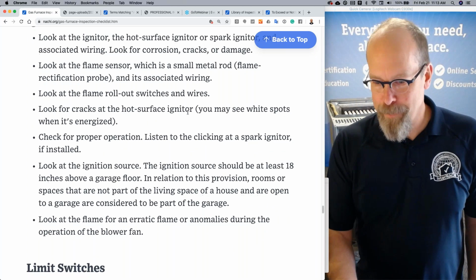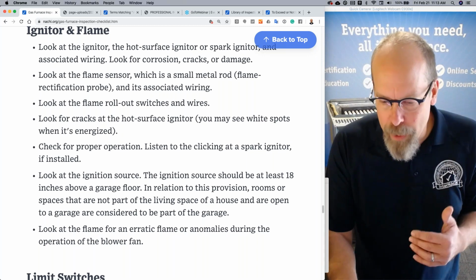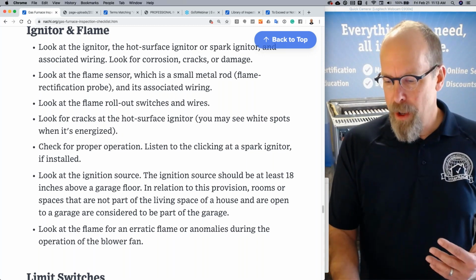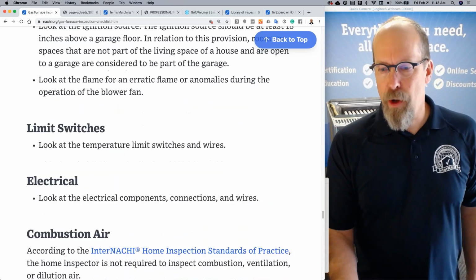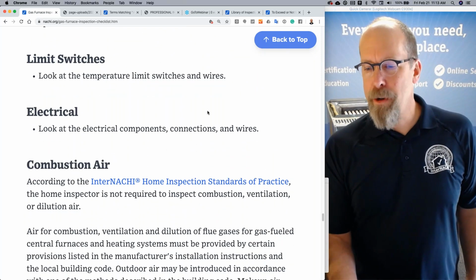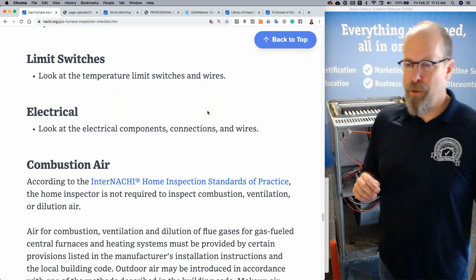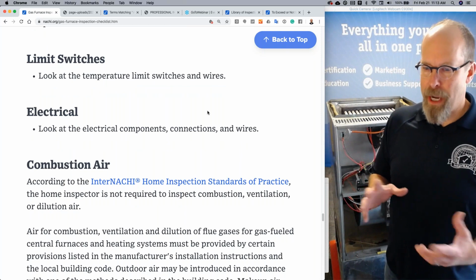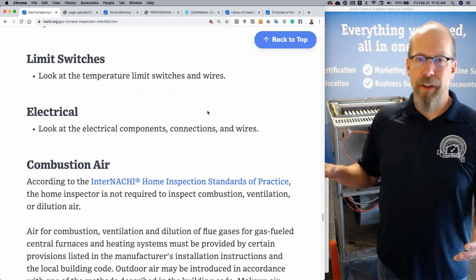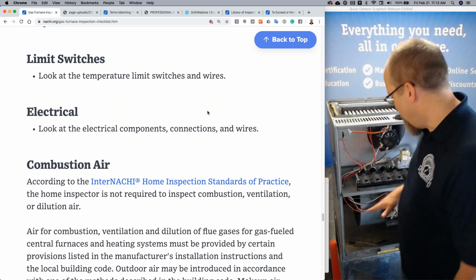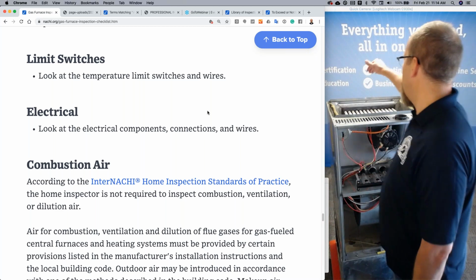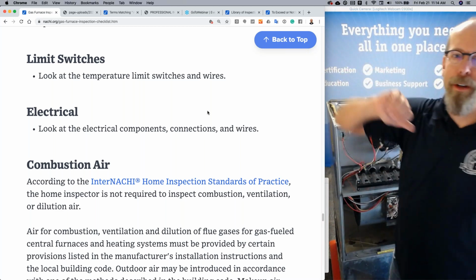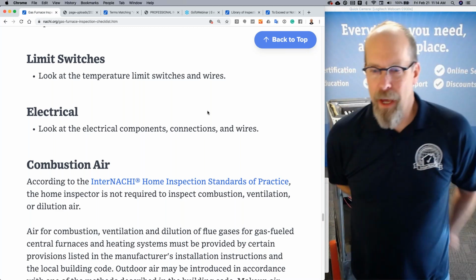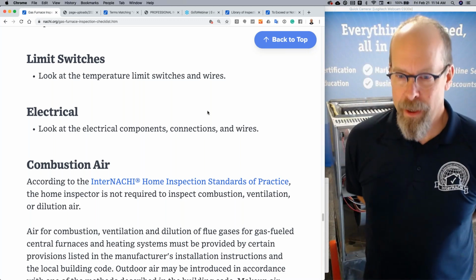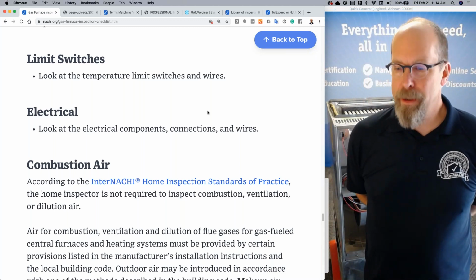So, you want to look for an erratic flame or anomalies during the operation of the blower fan. I personally have never been able to attribute or diagnose, with the help of an HVAC technician, a moving flame with an obvious crack in the heat exchanger. So just be careful with that. Sometimes flames move. Limit switches: look at the temperature limit switches and wires.